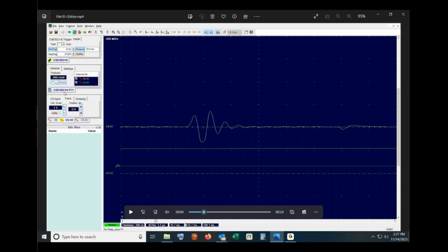What I'm going to do now is start the video again, and we're going to zoom in vertically by a factor of 100 to demonstrate. This is a 14-bit digitizer. If this were an 8-bit digitizer, that would mean there are 2 to the 8, which is 256, digitizer levels spread across this plus or minus 1 volt range. I should note that the vast majority, virtually all, not all, but almost all standalone box oscilloscopes are 8-bit devices. So most of them will have, as I say, 256 levels distributed across the input range.